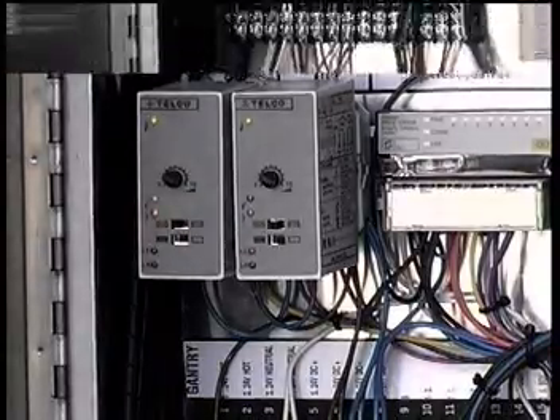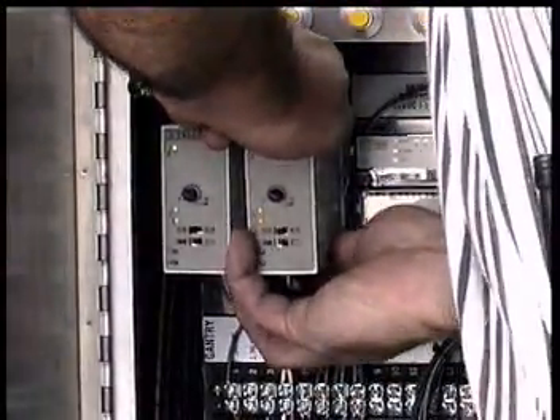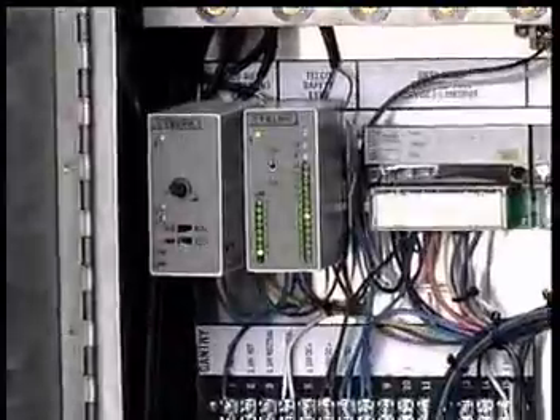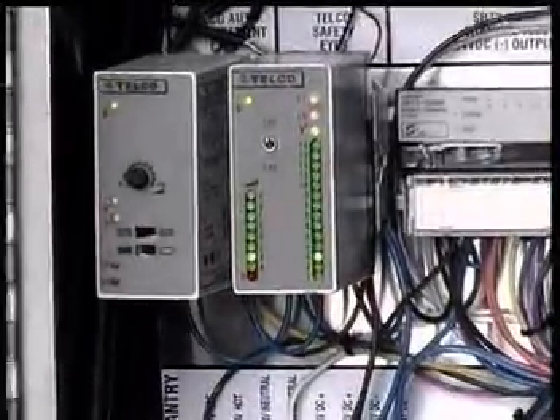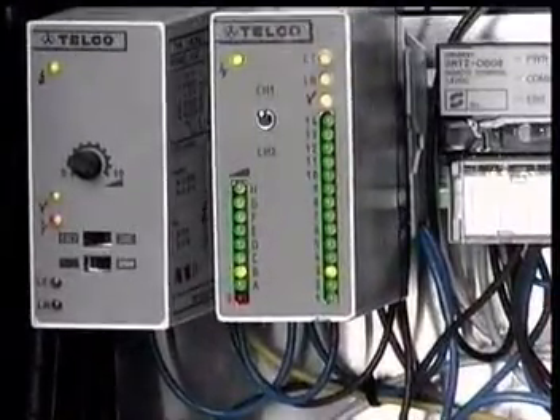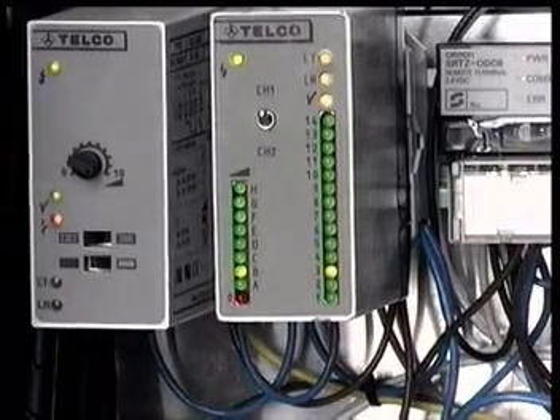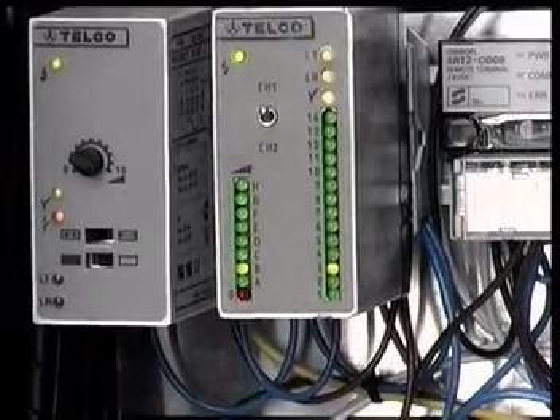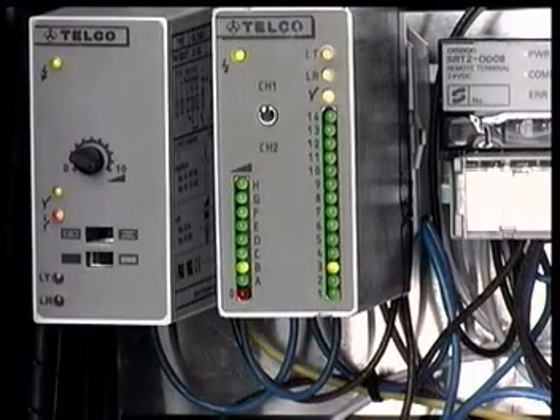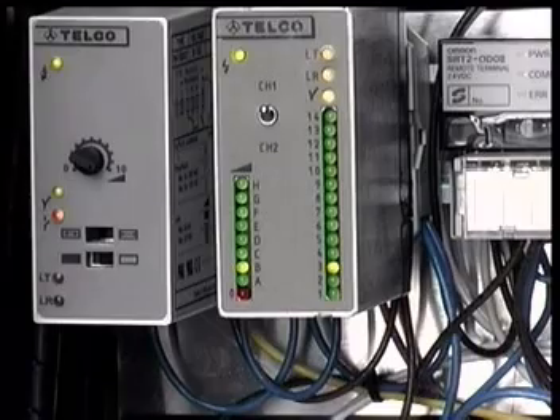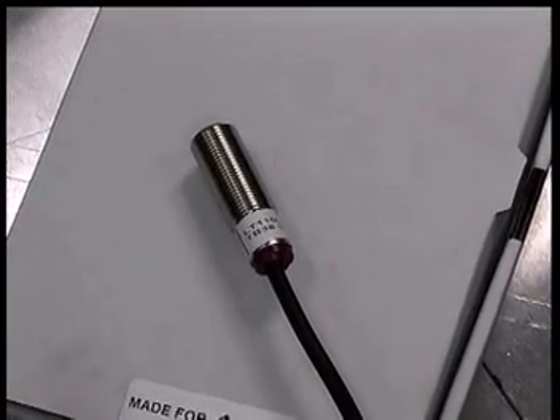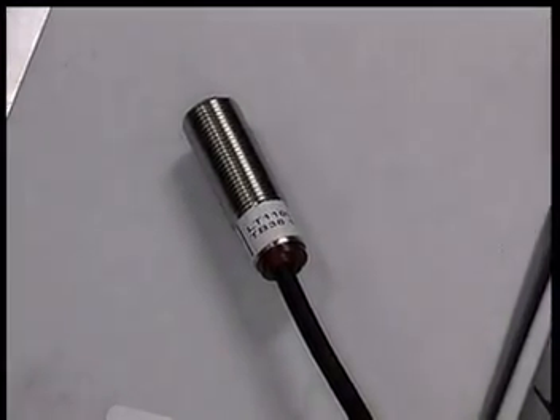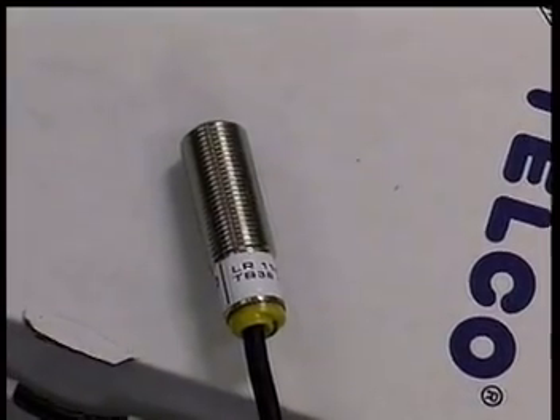If the amplifier lights are okay and on-off status does not change when the gantry eyes are blocked, check for eye alignment using the Optic tester tool. Replace one of the amplifiers with the Optic tester. Indicator light should be between A14 and B1. A14 is the best possible signal. B1 is the lowest acceptable signal strength. If the eyes will not read, replace receiver eye. On the telco eyes, the letters LT are on the transmitter and LR is on the receiver.